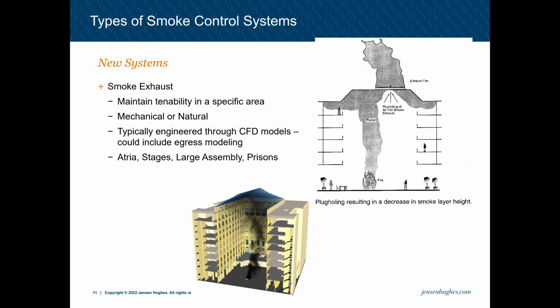Large assemblies such as stadiums. We'll hear the term smoke protected assembly seating. So if we're in an enclosed stadium and we don't have a lot of egress width in our aisles, the IBC, and if you're in other jurisdictions that work with the Life Safety Code, require you to have an engineering analysis to make sure that the same items as the atria and the stages, that we're maintaining that tenability.